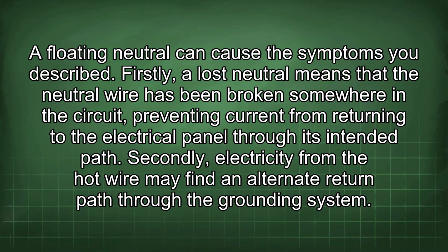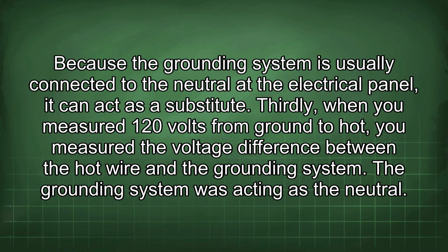A floating neutral can cause the symptoms you described. Firstly, a lost neutral means that the neutral wire has been broken somewhere in the circuit, preventing current from returning to the electrical panel through its intended path. Secondly, electricity from the hot wire may find an alternate return path through the grounding system. Because the grounding system is usually connected to the neutral at the electrical panel, it can act as a substitute.